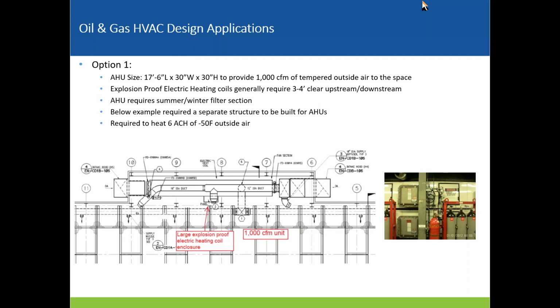So looking into option 1, the air handling unit size came out to 17.5 feet long by 30 inches by 30 inches to provide 1,000 CFM of tempered outside air. The explosion-proof electric heating coil is really what's driving that 17.5 feet length, with the 3 to 4 feet clear upstream and downstream requirement for those. So the example below is a real example. It's an outline.